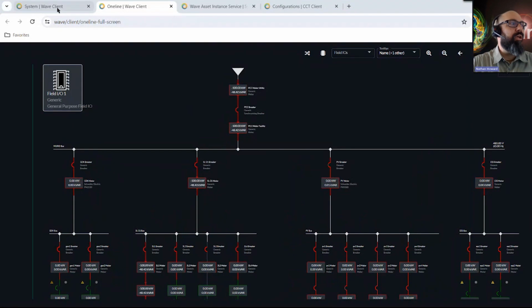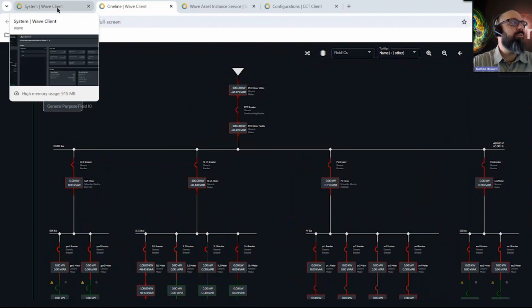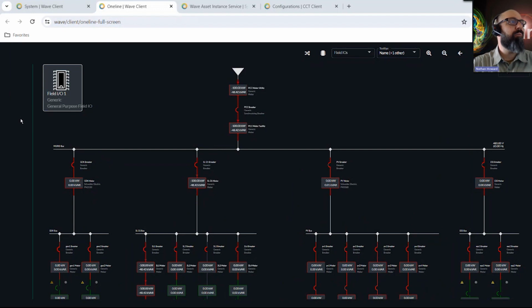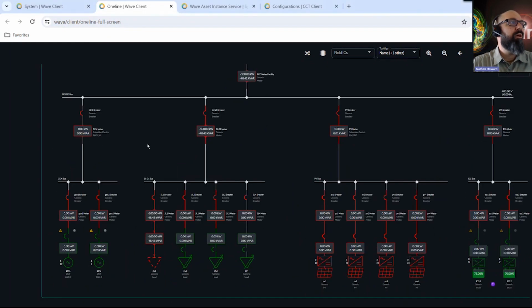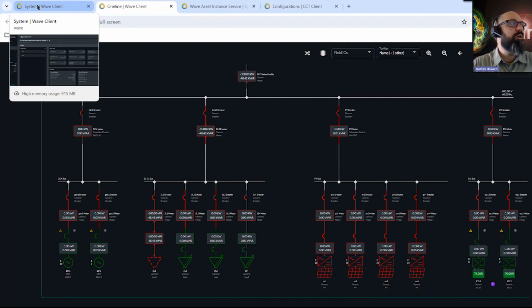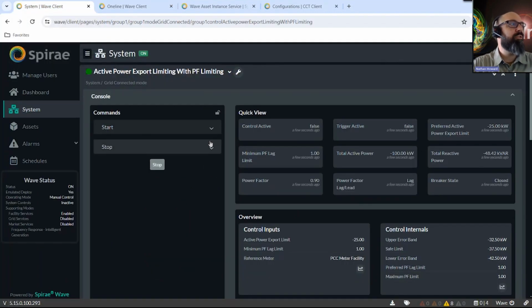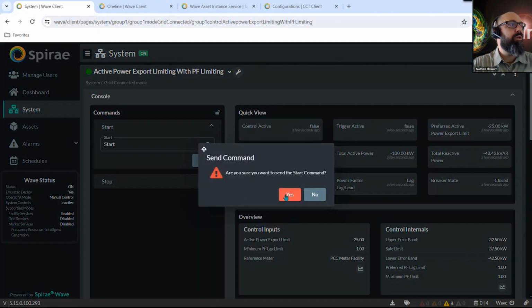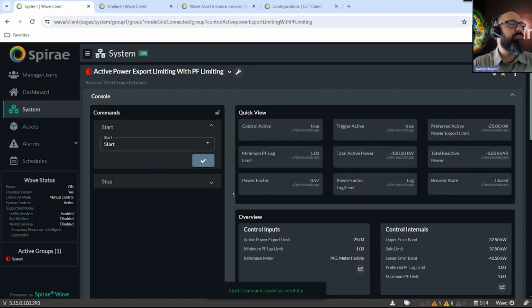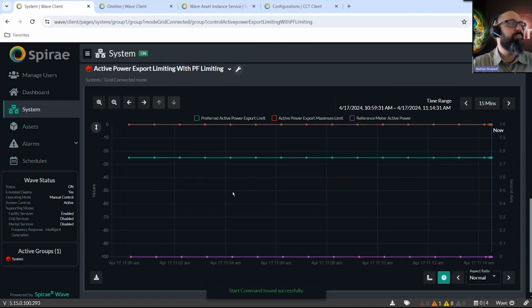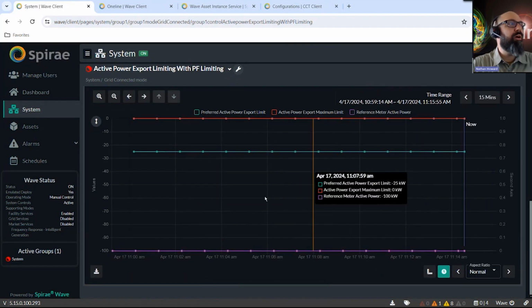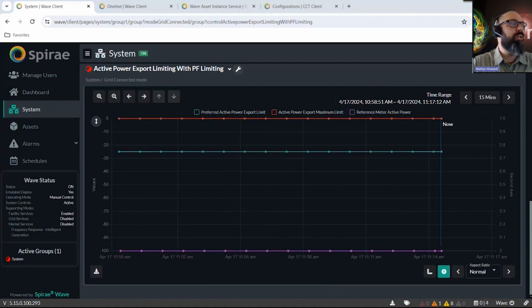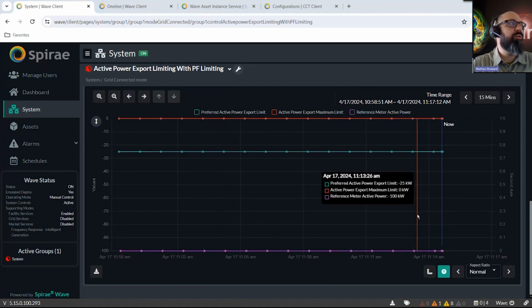Great. All right, so once again, we've got that primary load for the system being fed from the grid. In this scenario, we're going to be looking at the export limiting control. So we'll go ahead and get that started. And then we'll take a look at the trend screen for this control in the Wave interface. And we can see some key limits that we've set up here. So the red line up at the top, that's actually at the zero active power limit. So that's our zero export requirement from the utility.